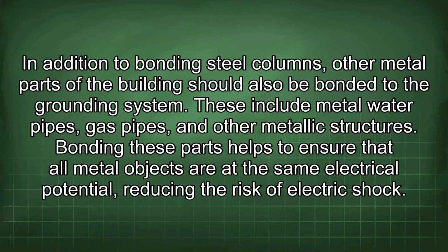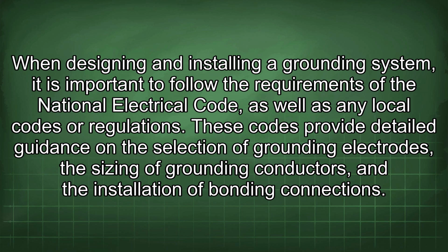In addition to bonding steel columns, other metal parts of the building should also be bonded to the grounding system. These include metal water pipes, gas pipes, and other metallic structures. Bonding these parts helps to ensure that all metal objects are at the same electrical potential, reducing the risk of electric shock.